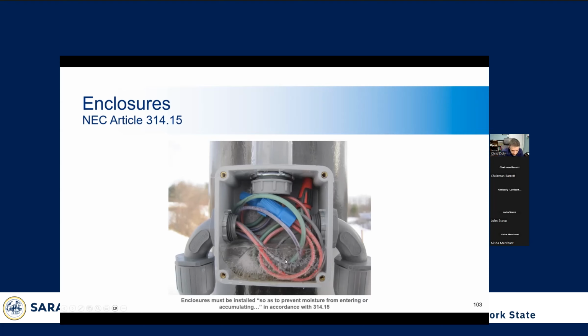But the only reason they could see this was because it was removed in the winter, and obviously this is ice down here. But what happened is water filled up this junction box to a point where it got high enough and it could go down one of these conduits on the side. It looks like the one on the right. And obviously water is not something you want in your electrical system. That can be quite hazardous. So that's a pretty bad mess up. So they would want to reinstall this junction box properly so that water doesn't get in.